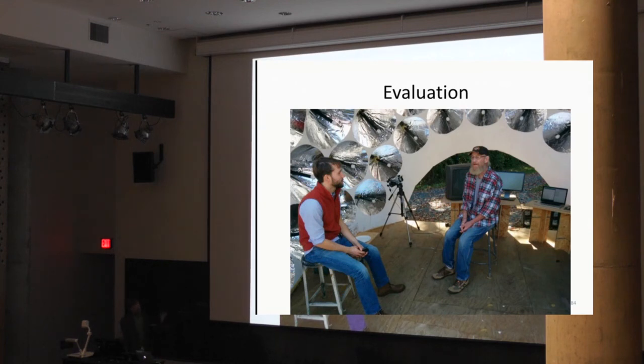Right now, overall, even on a relatively humid day, we get about a 10-degree cooler temperature into the bulb, which results in about a 5-degree shift in the mean radiant temperature. So people sitting inside could perceive a colder temperature than their actual temperature, but unfortunately, by the time it took to set everything up, the weather got cold again. So now we're reversing everything and setting it up for heating to try to run some tests, although there are other challenges in terms of how you heat the outside — it's a little bit colder than it is warm.